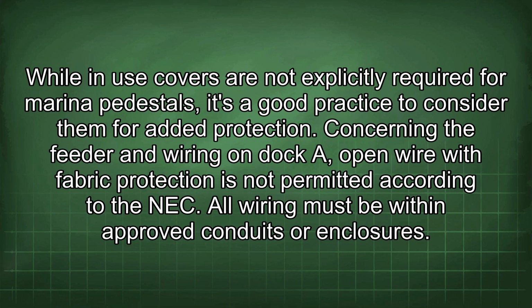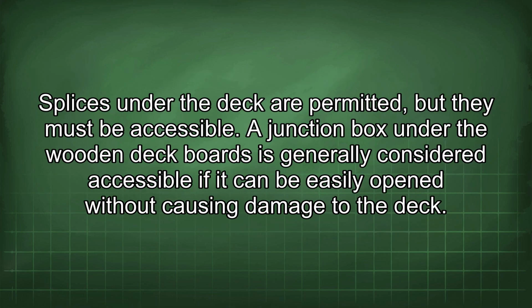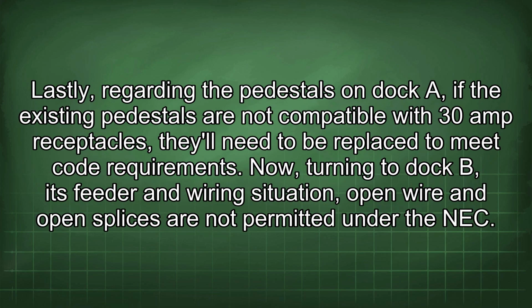protection. Concerning the feeder and wiring on dock A, open wire with fabric protection is not permitted according to the NEC. All wiring must be within approved conduits or enclosures. Splices under the deck are permitted, but they must be accessible. A junction box under the wooden deck boards is generally considered accessible if it can be easily opened without causing damage to the deck. Lastly, regarding the pedestals on dock A, if the existing pedestals are not compatible with 30 amp receptacles, they'll need to be replaced to meet code requirements.